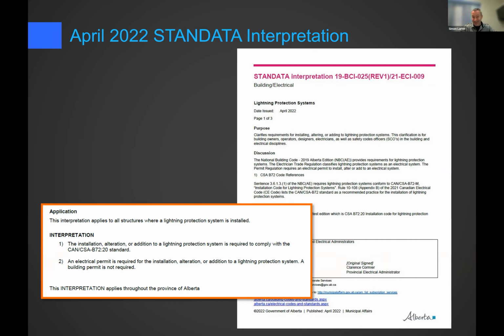I'll tell you why this was an issue for me personally, and for us as an industry in general: lightning protection goes on roofs, and roofs get redone every now and then. When roofs are redone, often the roofer doesn't bother to call the lightning protection contractor — they'll yank the stuff off and put it back the way it was. In my entire 25-plus year career, it has never once been put back the way it was. Not once, which is a problem — you are materially compromising the safety of that building.